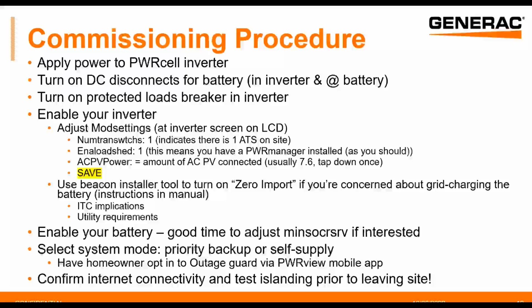Absolutely recommend that the last thing you do before you leave is just test islanding, shut off power to the house, make sure the transfer switch flips, which would indicate all your settings are good. You should see the battery supplying power to the house. I would wait at least 5 minutes, since in certain circumstances we may be able to frequency shift on the PV array while you're there. It kind of depends on the battery state of charge and how much load there is in the house.